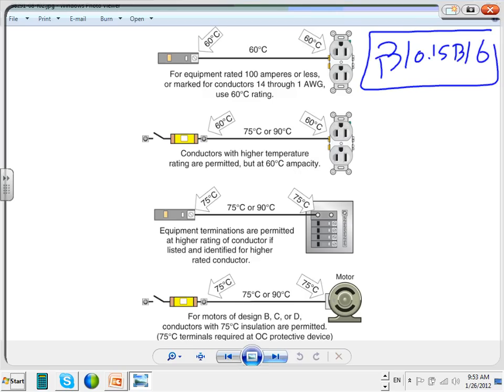When you have 310.15(B)(16), do you remember the rules that we said? I like it because it's a picture. Hopefully it will bring you home. Let's look at the first rule. Rule number 1: if the terminals are 60, the cable is 60, and the equipment is 100 amp or less, or with conductor number 14 to number 1, you defaulted to, can you see what? The 60-degree column. See the default that I told you about?